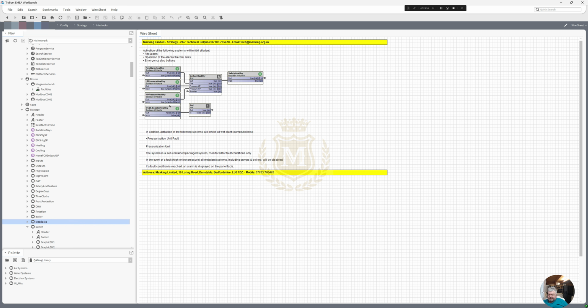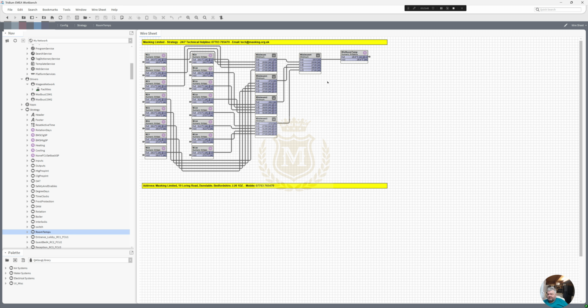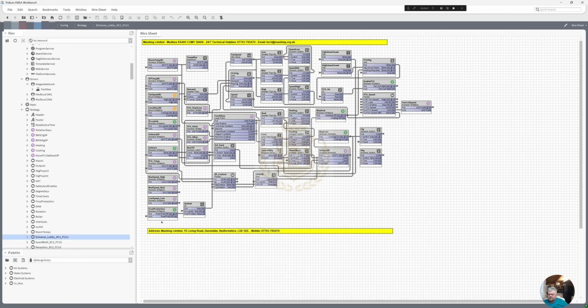Interlocks, pressurization, fire alarm, just into an AND gate. We've done the switches, room temperatures, so we're just taking the minimum room temperature, which is quite high, but I think it's about 23 degrees outside. And then entrance lobby fan coil unit, and the other fan coil units will be exactly the same. So this is where we can do the heating or cooling of the fan coil unit.